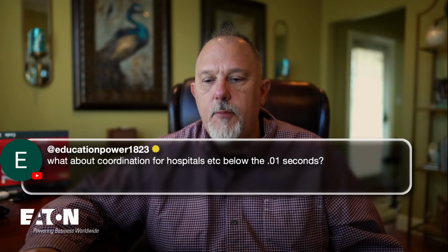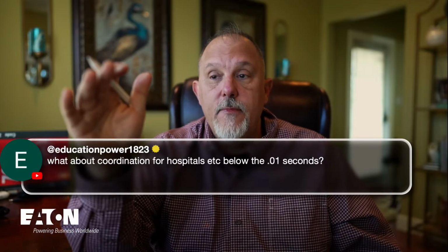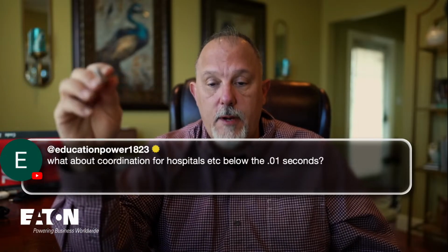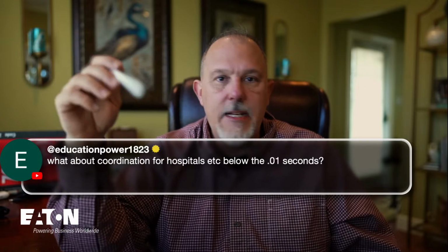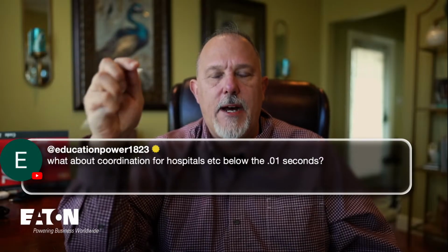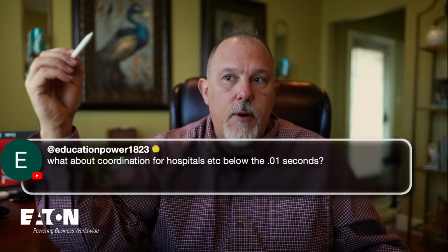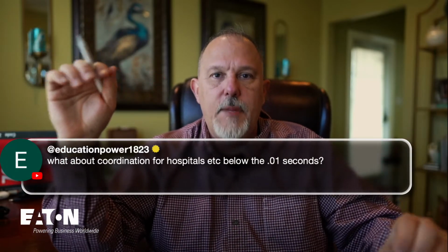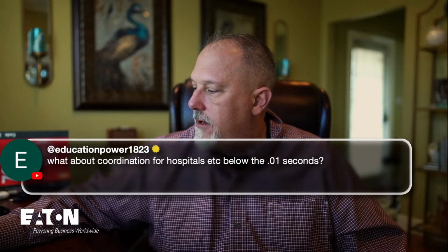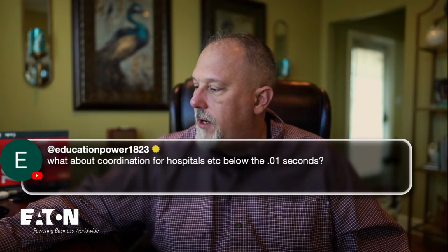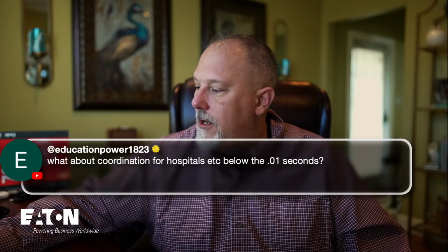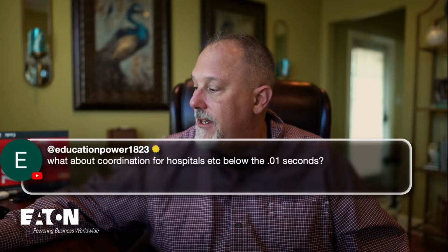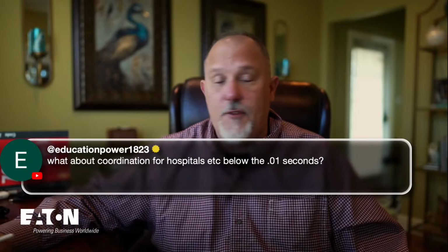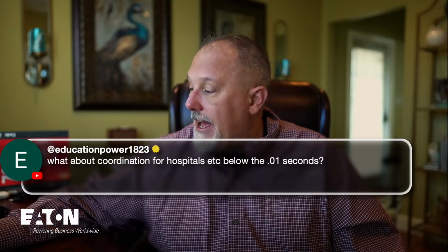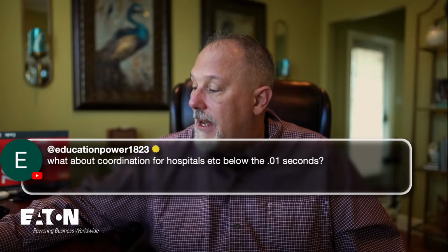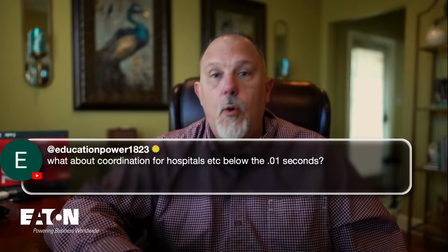What about coordination for hospitals below 0.01 seconds? Okay, here's my issue, Robert. In my opinion, don't ever mention time. When you say below 0.01 seconds, the discussion for healthcare is not about whether I go below 0.01 seconds or go to time zero. Time zero means nothing. Even at time zero, if I drew these two curves, let's delete everything below there. This is 0.01 seconds. If you say time zero, I don't have curves that go down to 0 seconds. If you could find curves that do that, I have coordination, I don't know. I stay away from saying time zero or to 0.01 seconds.